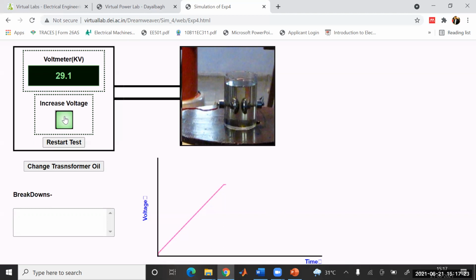The voltage is very suitable for that particular point, but from this instant, from 29.1, meaning after 29 kilovolt, this transformer oil starts facing issues, breakdown issues. We'll see, it will be a little bit.